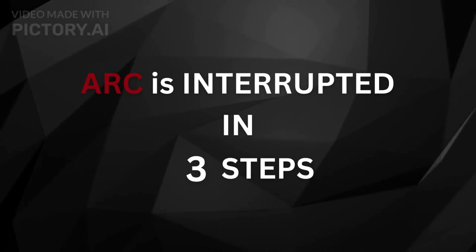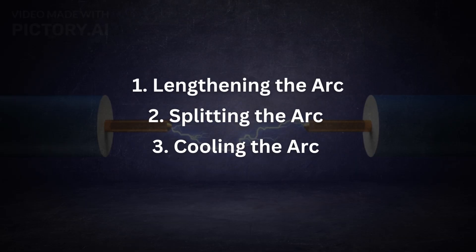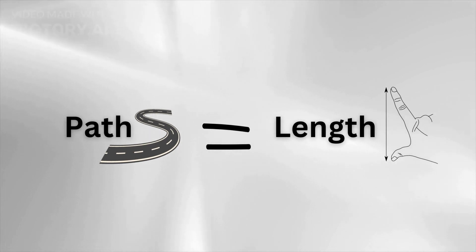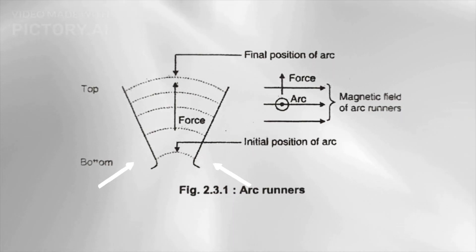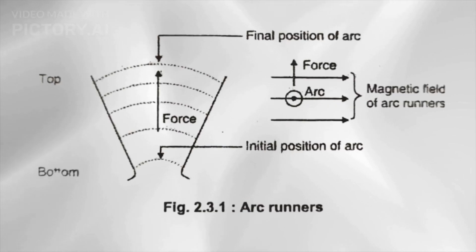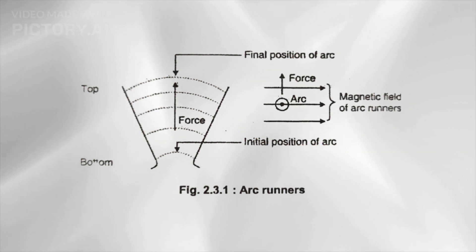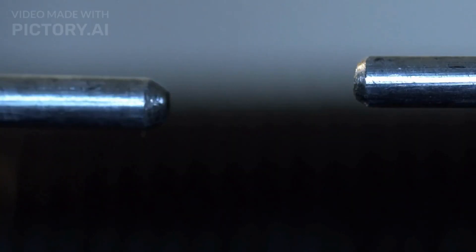In this method of arc interruption, we use three steps: lengthening the arc, splitting the arc, and cooling the arc. Step 1 — Lengthening the arc: The length of the arc can be increased by making it flow through a longer path. This is achieved by using arc runners, which are V-shaped blades made of conducting material. The arc strikes near the bottom portion of these blades. Due to the magnetic field created by the arc runners, the arc becomes a conductor placed in a magnetic field, and a force is produced on the arc in the upward direction, thanks to Fleming's left-hand rule. As the arc travels upwards, its length increases, resistance increases, current decreases, and the arc can be interrupted.